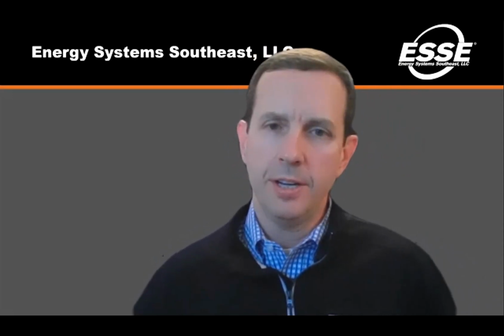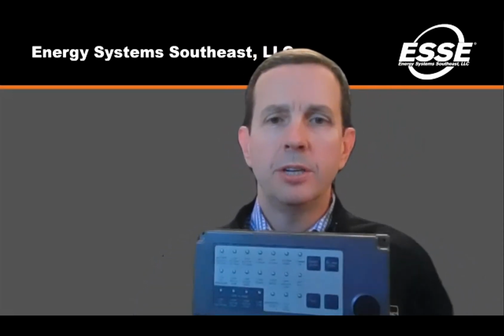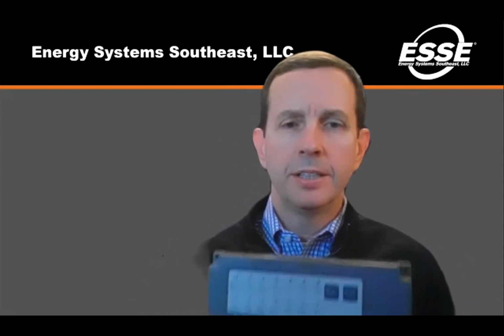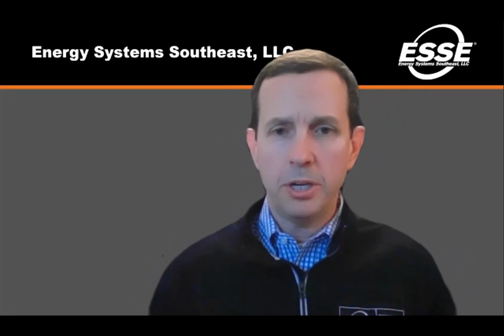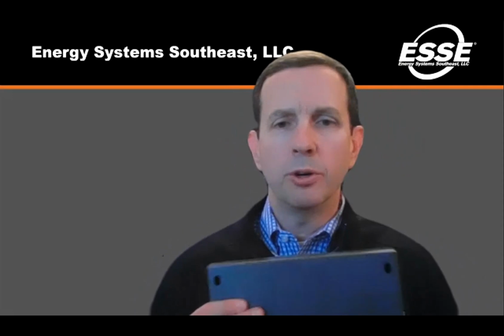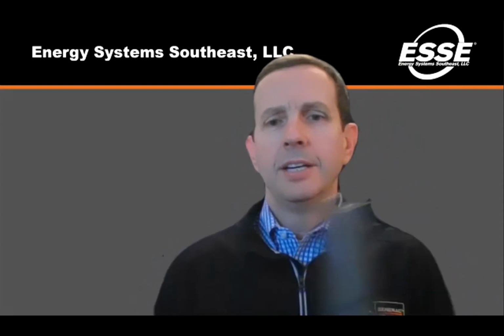Today I want to cover the Generac 21 Light Remote Annunciator. And this is an NFPA 110 remote annunciator. Take a look at it right here. I'm going to show you a close-up view here in a second with a picture. This is the surface mount version of the remote annunciator. As you can see, it has a knockout on the back. It also comes with an optional flush mount kit where the annunciator fits down into, and it mounts flush into the wall. The same knockout in the back will be in both devices.